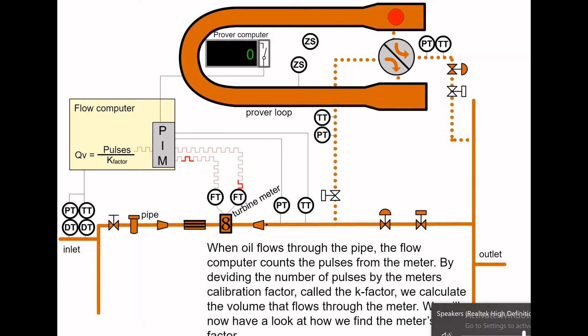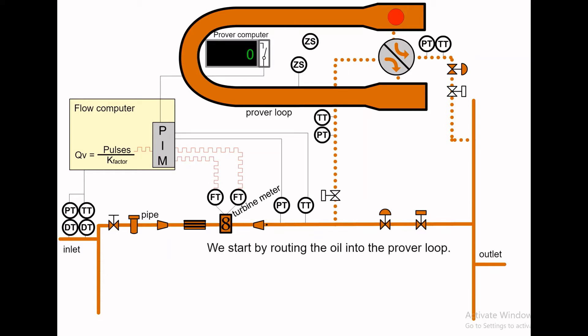We start by routing the oil into the prover loop. First we open the prover loop's outlet valve and then the inlet valve. The oil is now able to flow through the prover loop. Then we close the pipe's outlet valve and adjust the flow rate to the value it had before starting the calibration. The valves are checked for leakage and we check that the flow rate, temperature and pressure are within the scope.